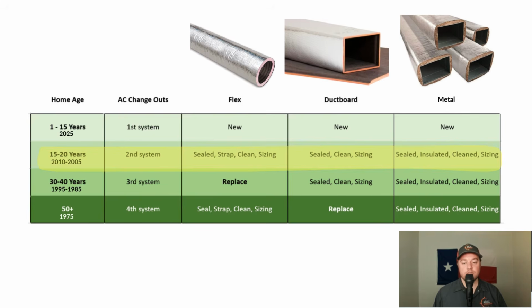Proper ductwork sizing is one of the most critical components when you're replacing an AC system, in order to get the full life of the system, remove as much humidity as possible, and get maximum efficiency. And let's say the ductwork is slightly undersized. A lot of times all you have to do is replace the plenums, install a couple duct runs, or enlarge a couple duct runs in areas where you're having trouble with airflow. Then you can reuse the rest of your ductwork. That way you're not shelling out a lot of money on ductwork that's still good.